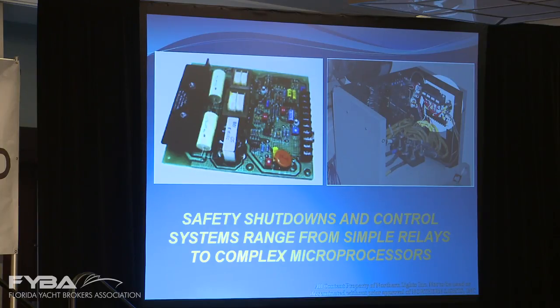In some commercial large generators that we build, class requirements ask that we install a water flow sensor to detect a stoppage in the water flow. It turns out that a lot of water flow sensors are easily tricked by air bubbles or things like that. So a water flow sensor typically is attached to some sort of an annunciator or warning rather than actually shutting down the generator, at least in the Northern Lights units. So water flow sensors sometimes require maintenance, and they should be checked periodically.